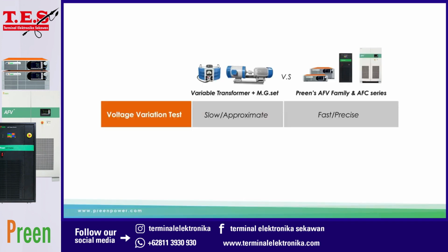According to our demonstration, the programmable power source has easier operation and more accurate measurement. Plus frequency adjustment is also valuable. On the other hand, the variable transformer has less convenient operations.